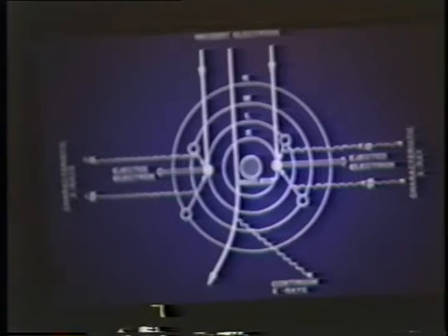Now, as can be seen from this diagram, the primary beam electron may pass very close to the nucleus of the sample atom and experience a large change in direction, but only suffers a very small energy loss. In the majority of collisions, the energy loss is less than 1 keV, although the energy distribution extends all the way to the energy of the incoming beam. So if this is, say, coming in at 10 keV, you would have an energy distribution all the way right up to 10 keV. Most of these low-energy X-rays are either absorbed by the specimen or remain undetected by the X-ray analyzer.